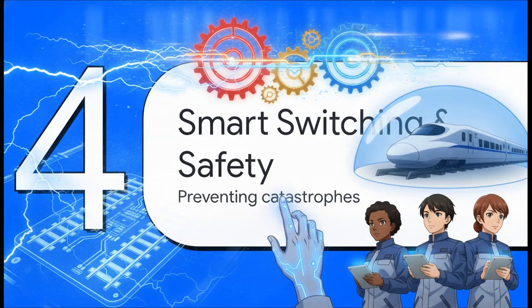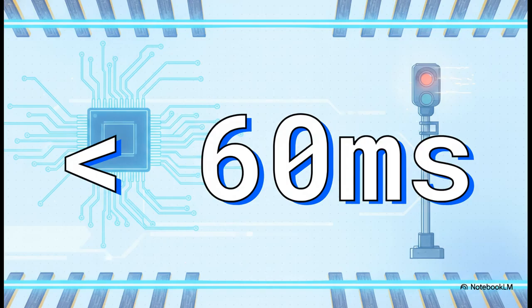All right, Section 4, smart switching and safety. So the absolutely crucial point here is this tiny measurement, under 60 milliseconds. The system features a microcontroller-based static auto changeover switch. If an inverter fails, this static switch swaps over to a backup power source in less than 60 milliseconds. That is literally faster than the blink of an eye. It's so incredibly fast that a signal lamp out on the tracks won't even flicker.